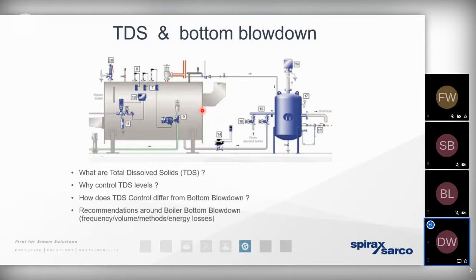It will be replaced with cold water, and we'll need to add more energy to it to bring it up to the point where we can start producing steam again. So we can either perform that bottom blowdown manually, but it's far, far better if we can move towards a system whereby we've got a timer on an actuator that is going to open for the prescribed number of seconds. And if we know the pressure of the boiler and the number of seconds that the valve is open for, we can determine exactly how much hot water we're dumping to waste. We can keep those inefficiencies to a very, very low point.